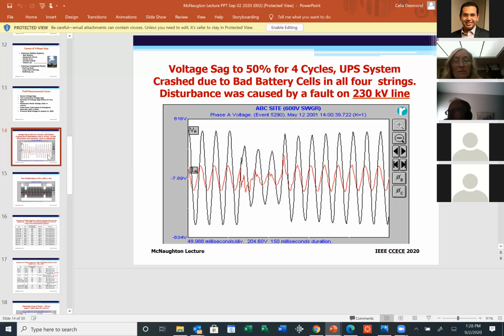This one shows, just look at this one. This is an event where the waveform shrank, and basically we have a voltage sag. Here it was about 50%. This event was caused by a fault on what we call a 230 kV overhead line. And this event only lasted 4 cycles, which is 66 milliseconds.